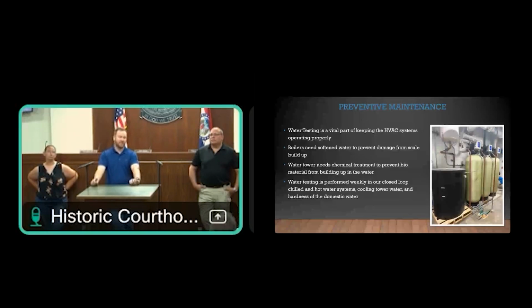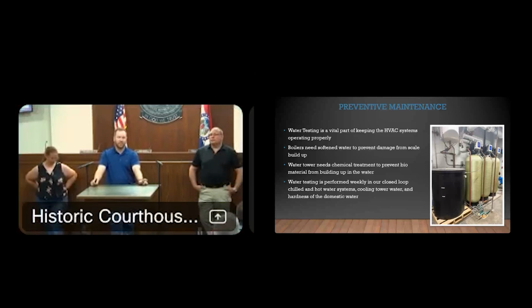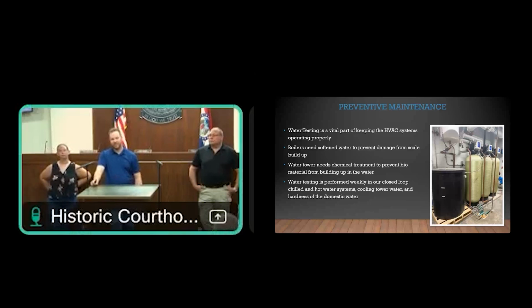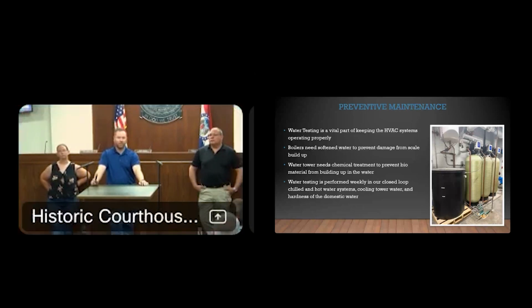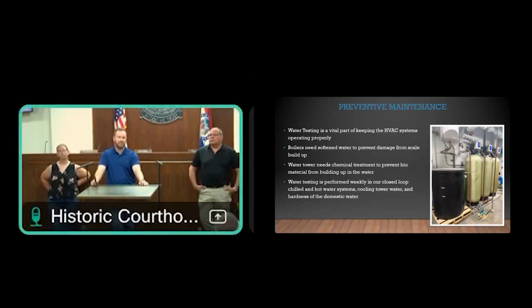And then, as you can imagine, with all that water that goes through the building, water testing is important to make sure that the water running through all the pipes is able to do the job that it's put up to. So our PM department also does water testing. Our boilers need softened water so they don't scale up, so that we have them long term and they don't have issues before they should. Our water tower needs chemical treatment to prevent things like algae from growing in it. And then we test our water weekly to make sure that everything is up to par.